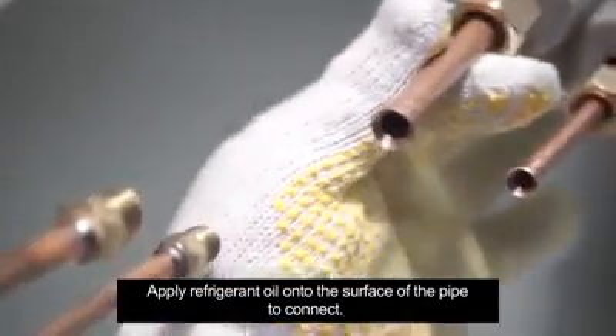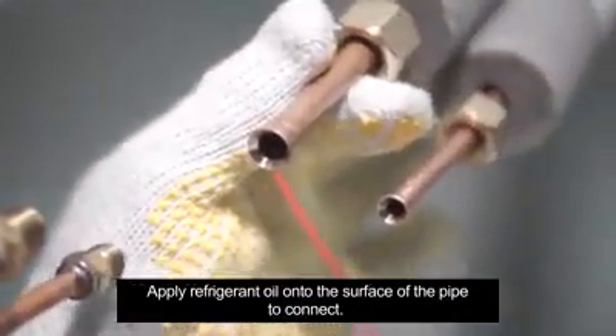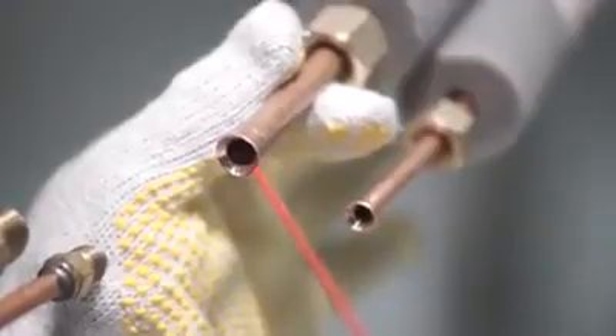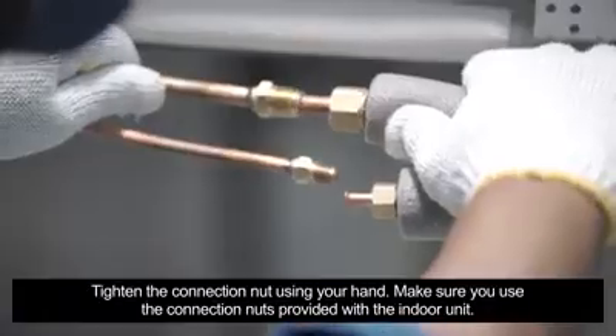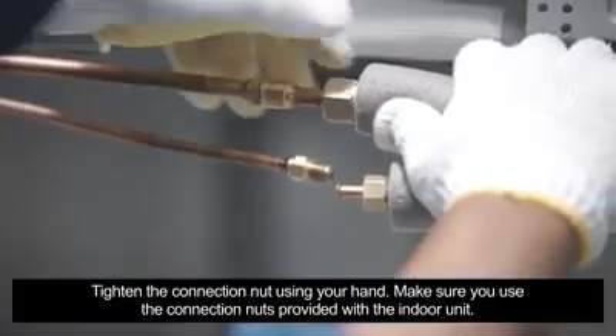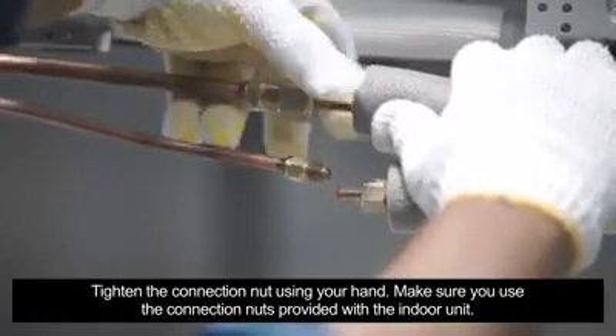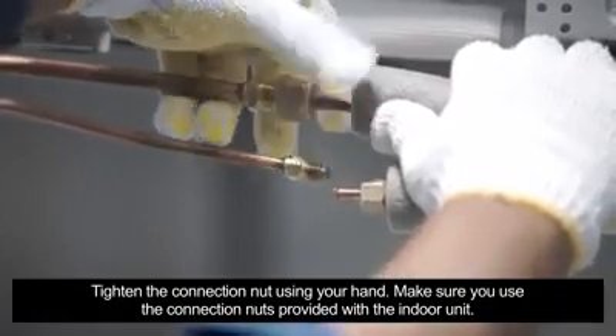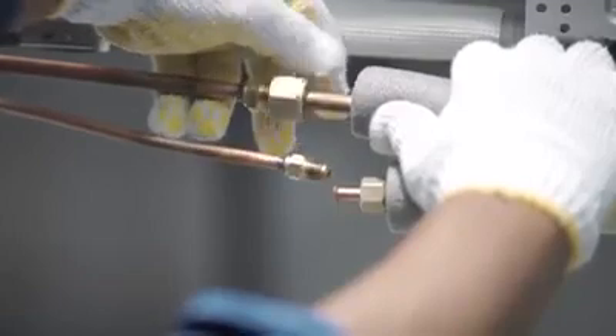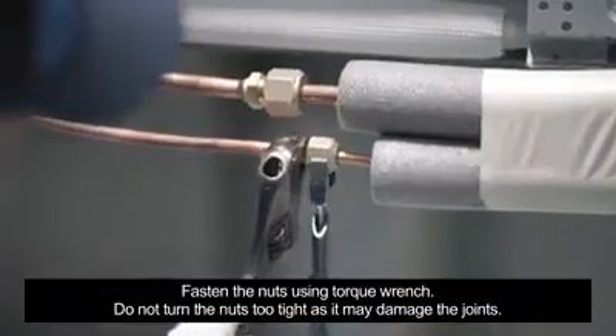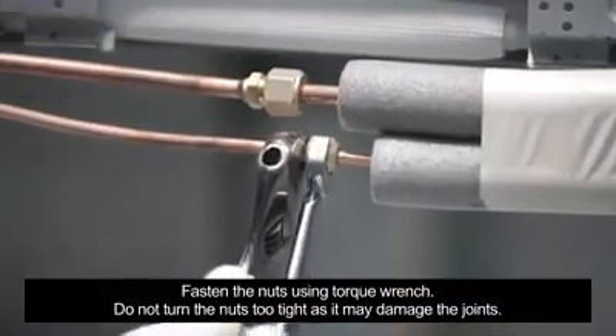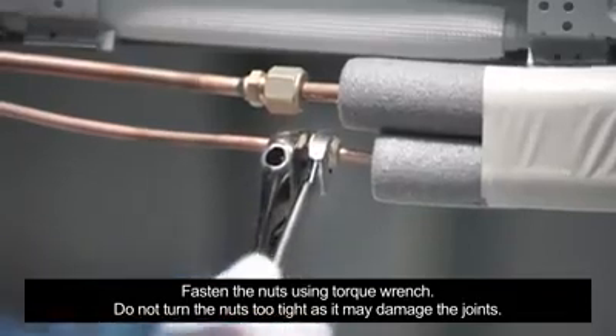Apply refrigerant oil onto the surface of the pipe to connect. Tighten the connection nut using your hand. Make sure you use the connection nuts provided with the indoor unit. Fasten the nuts using torque wrench. Do not turn the nuts too tight as it may damage the joints.